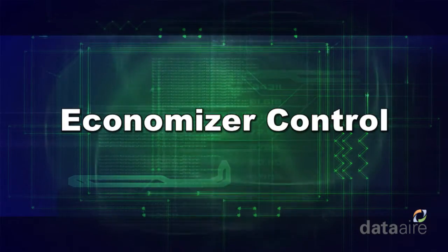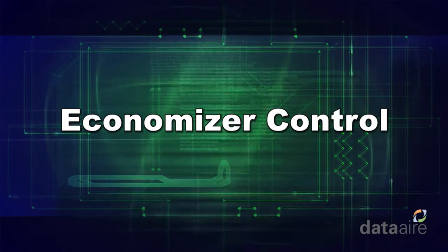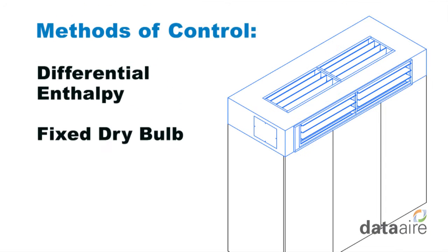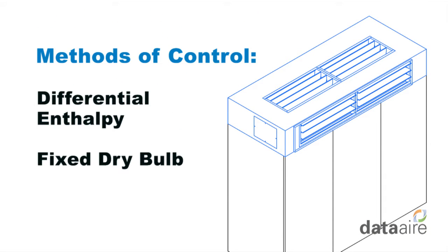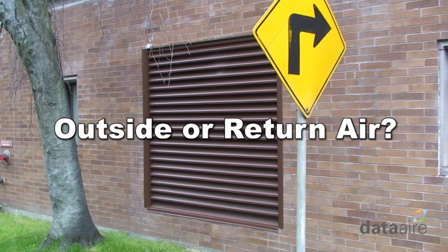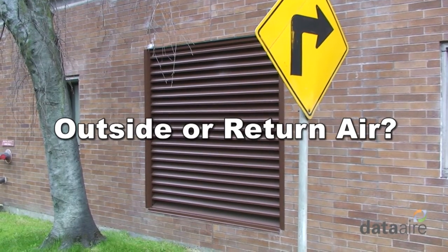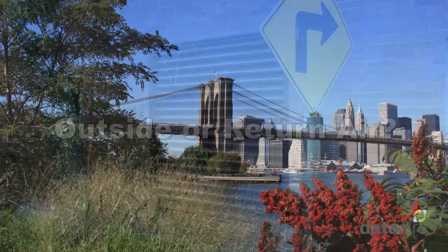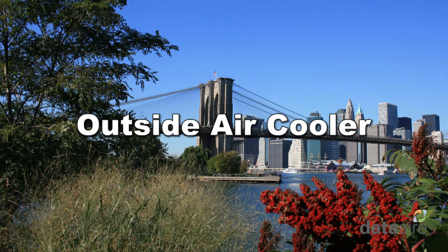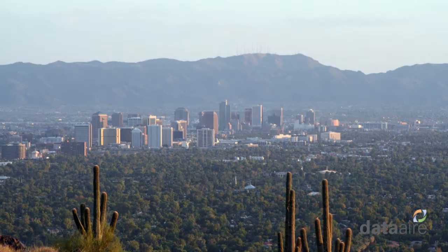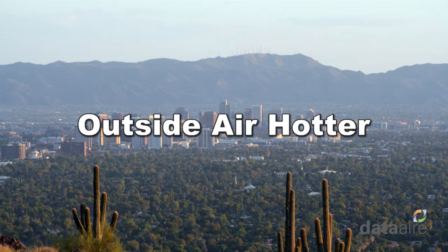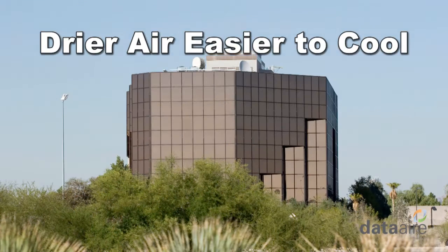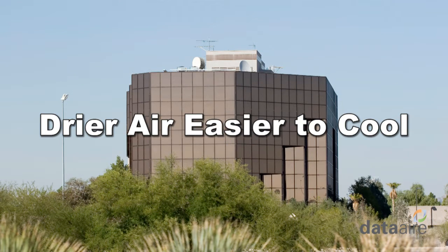Data Aire provides two methods of determining how to control the economizer: differential enthalpy or fixed dry bulb method. The differential enthalpy method, enthalpy being the measure of the total energy in the air, determines whether the outside air or the recirculated return air is more efficient to cool. This could occur when the outside air is cooler than the return air, or even if the outside air is hotter but drier than the return air.